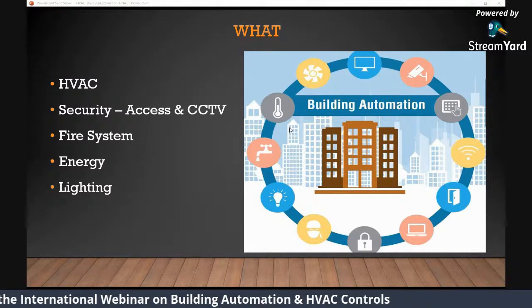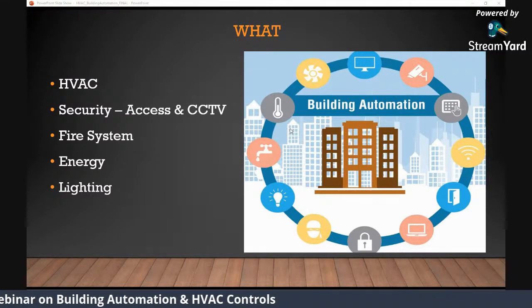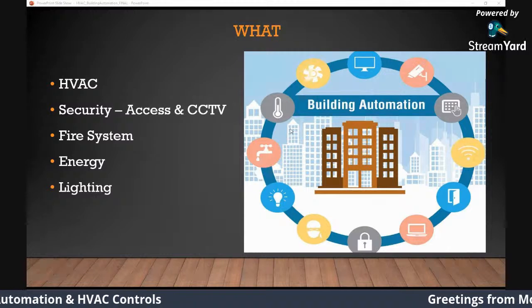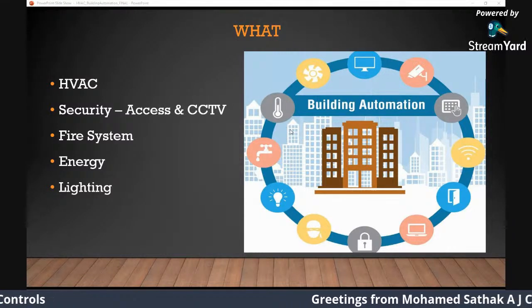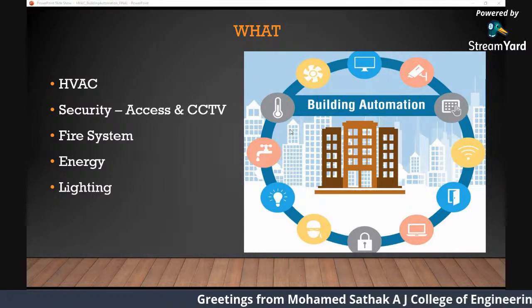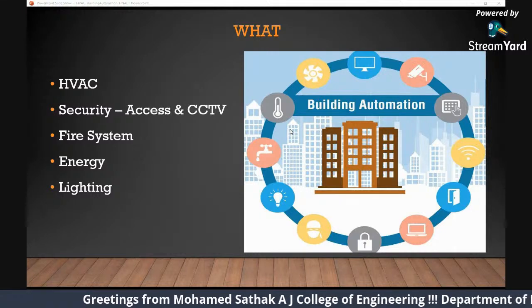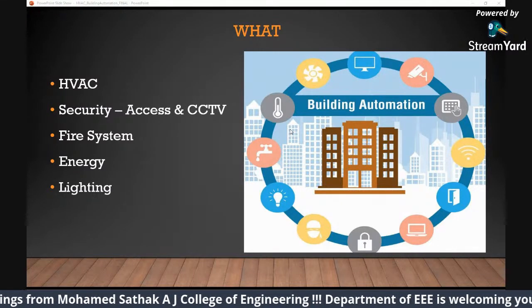You install the system, you control it. There are multiple controllers, devices, sensors. You have to design it and program it accordingly so that the building runs on its own without anyone's operation. All you have to do is design it accordingly, and it's going to take care of its own.